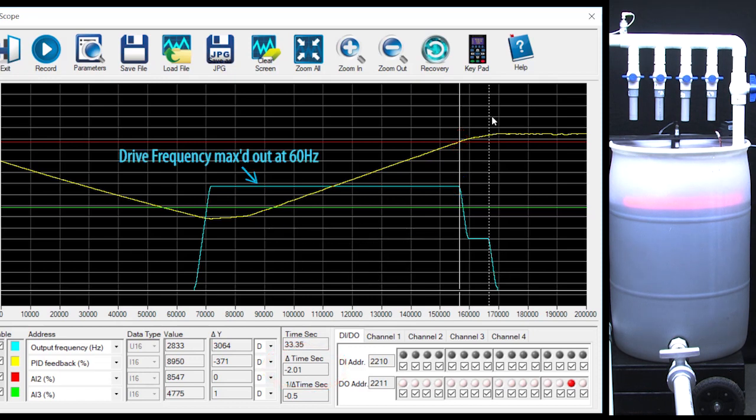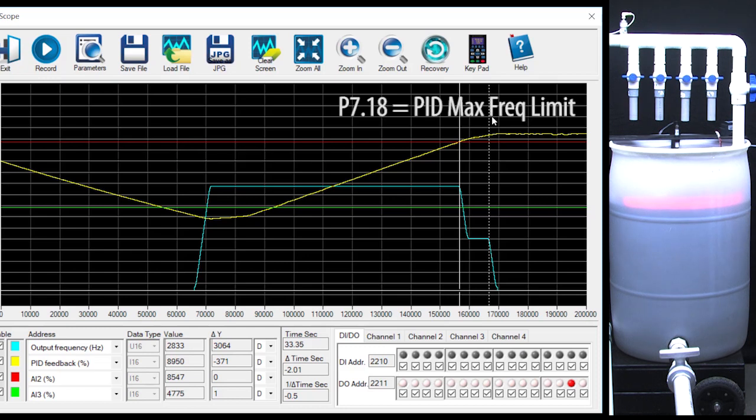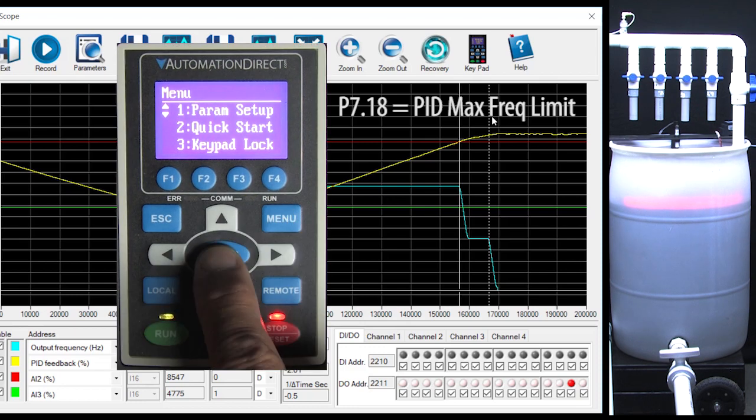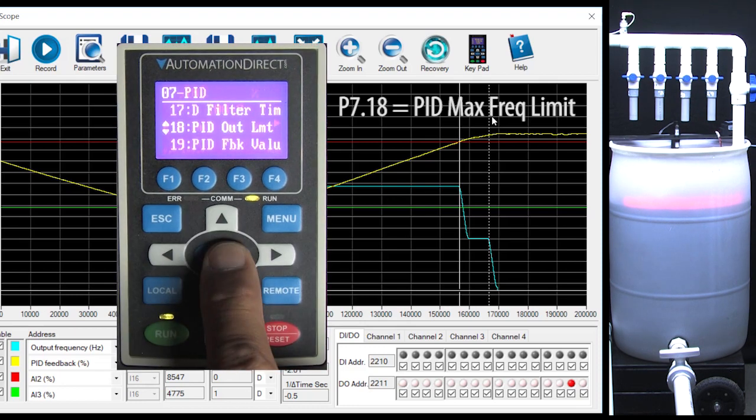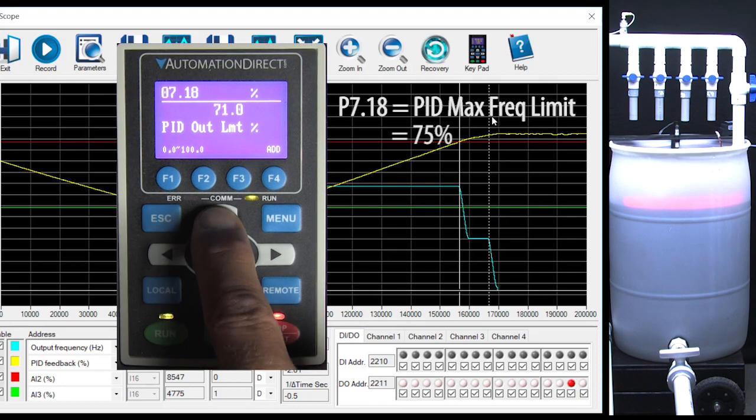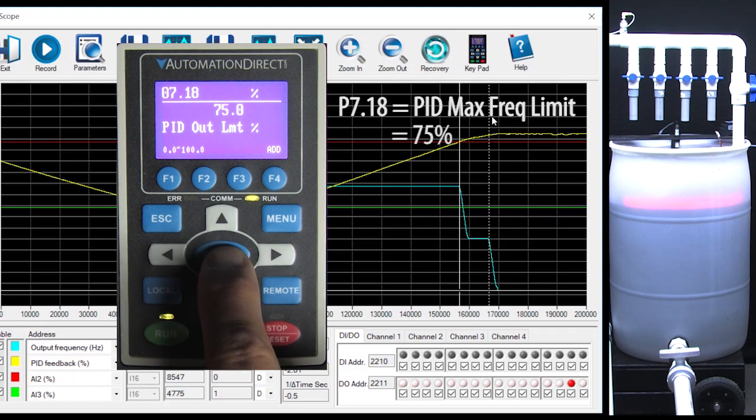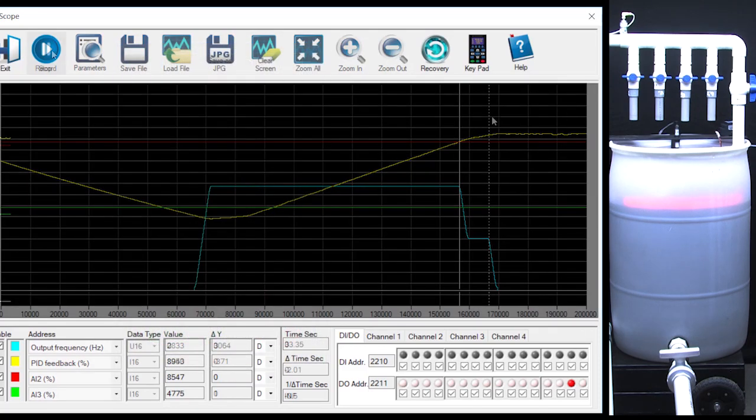Did you notice that PID is pushing this drive really hard to get the tank filled back up? What if you don't want the motor to run at the full 60 Hz? Well, just set the PID output frequency limit to whatever you want. Let's set that to 75% and hit run.